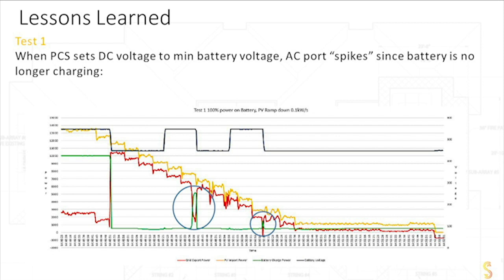Now, this is a worst case scenario. An engineer or a product manufacturer should never design a system that allows this hysteresis or this repeating motion to go on and on and on. Really, what would happen in nominal, normal operations is the battery would never turn on and charge at this level to begin with. It knows the rules. It doesn't need the inverter to tell it. We're all monitoring with the same data on the same system. So effectively, this doesn't happen in real life.